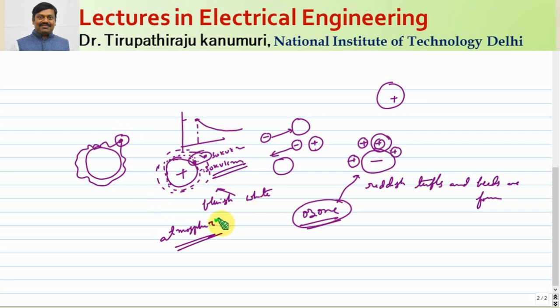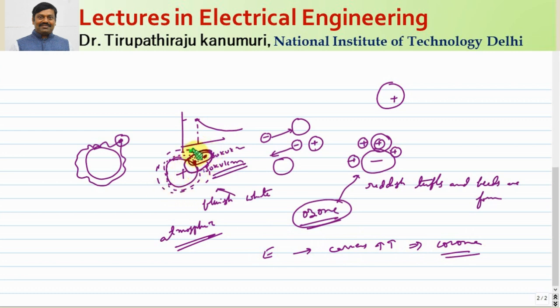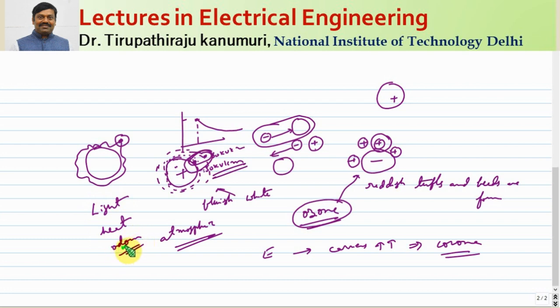Corona also depends on atmospheric conditions — in stormy or rainy weather, more charge carriers are already present in the air, so the corona effect is greater for a given electric field. The energy required to ionize the air and set these charges in motion comes from the supply, meaning some energy is lost in the corona phenomenon. This energy is dissipated in three forms: light, heat, and the characteristic ozone gas.